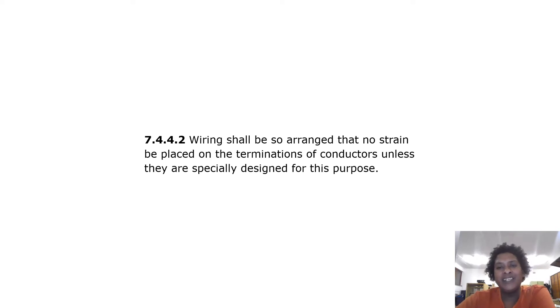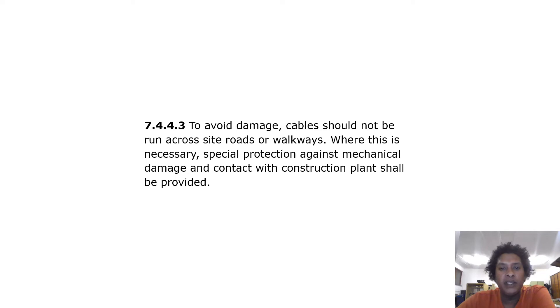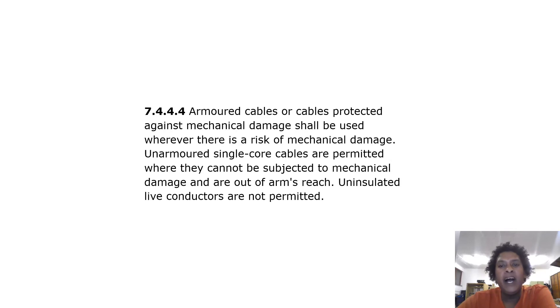Wiring. Wiring shall be so arranged that no strain be placed on the terminations of conductors unless they are specifically designed for this purpose. To avoid damage, cables should not be run across site roads or walkways. Where this is necessary, special protection against mechanical damage and contact with construction plant shall be provided. Armored cables or cables protected against mechanical damage shall be used wherever there is a risk of mechanical damage. Unarmored single core cables are permitted where they cannot be subjected to mechanical damage and are out of arms reach.